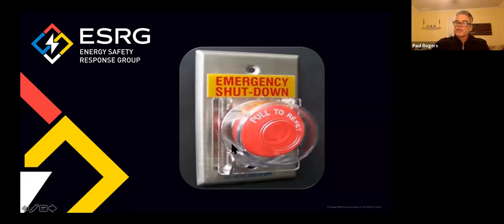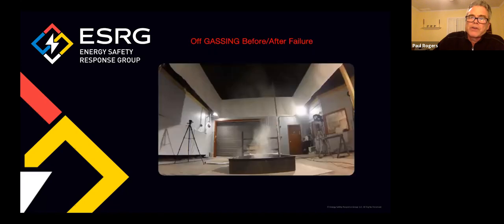Even though you shut these things down, you don't dissipate the energy. The energy is isolated, it becomes stranded, and that's huge for the fire service. Whenever we have an electrical emergency, field communication tells people on the ground, hey, power is shut off, and then we start to operate. But with energy storage, you can shut the power off and stop charging and discharging, but you did not lose the energy. So that energy stays stored there, and we call that stranded energy. That's really important for you to understand if you're a first responder.